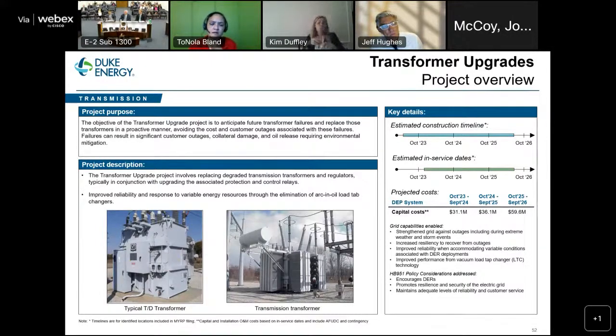One of the key things this project eliminates is a vulnerable arc in oil design for load tap changers. As we see more and more renewable energy resources, and particularly variable energy resources, connect to the grid, this arc in oil technology is a specific vulnerability. But essentially, it's an oil tank where, again, similar to a breaker, as a voltage regulator or a transformer controls voltage, there's an oil tank where this arcing occurs. Gases can accumulate in that oil tank over time and lead to catastrophic failure.